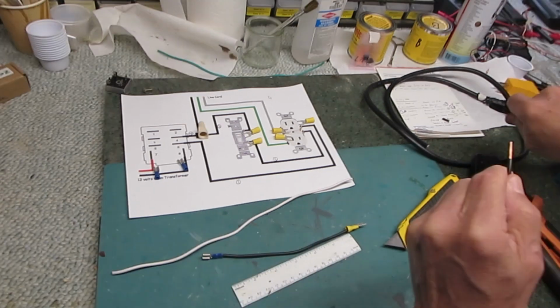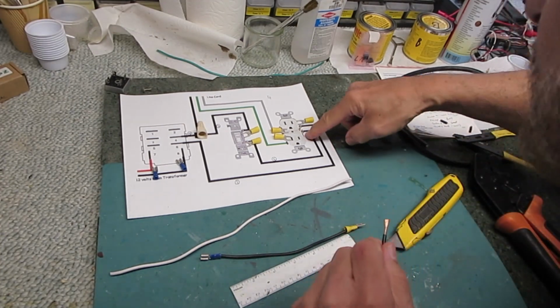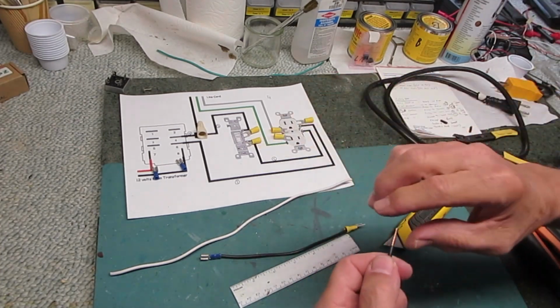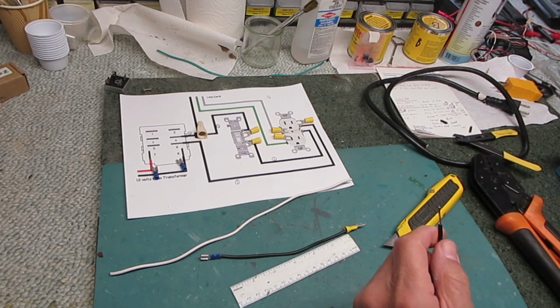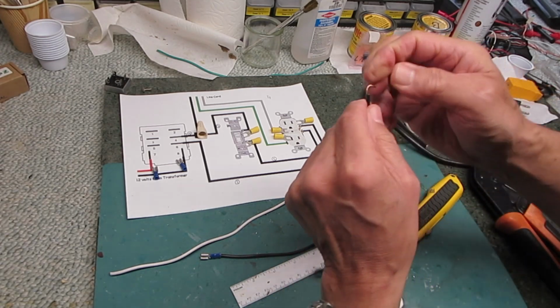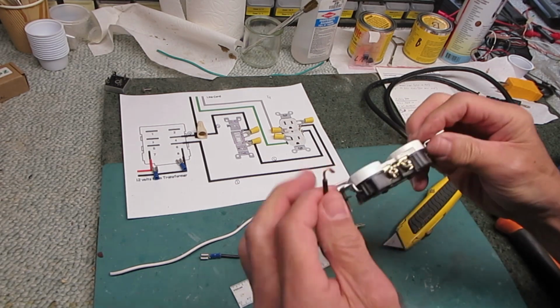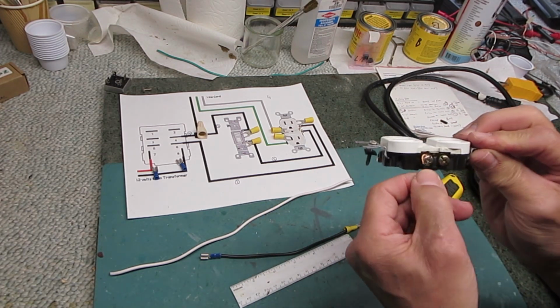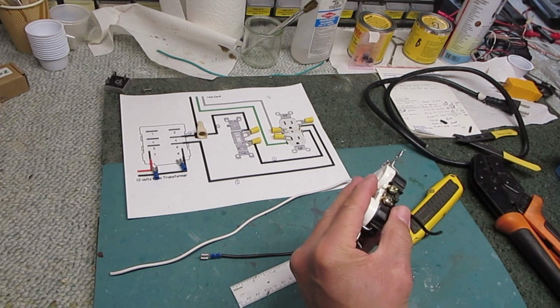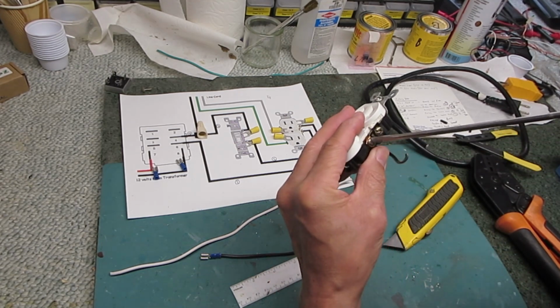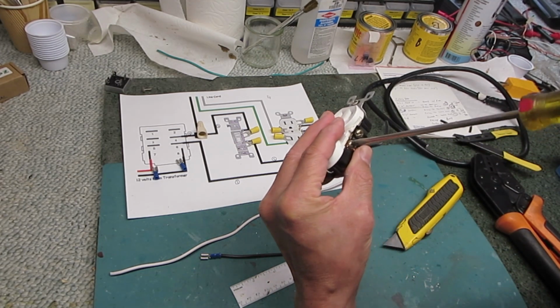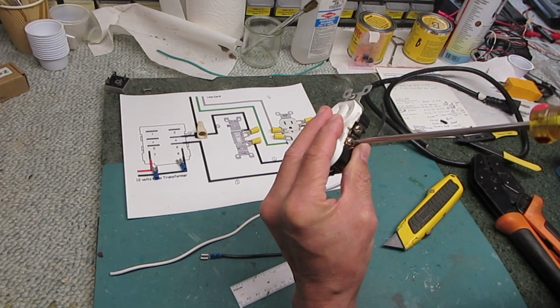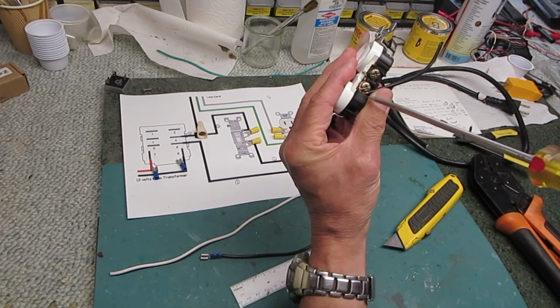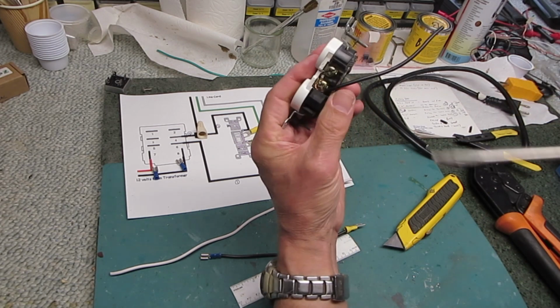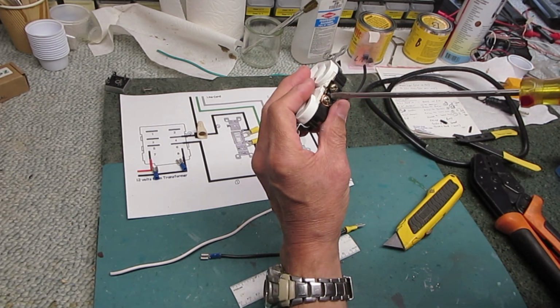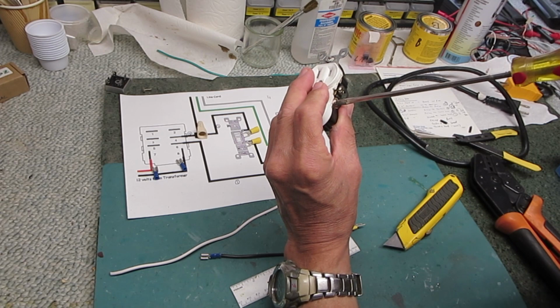This is going to be wire number 2, which is going to go from the receptacle to the switch. Now, if you just take this wire and make a hook in it and try to put it around the screw, it tends to spread the strands out and push it away from the screw. You can see it's coming out around there, and it's not really a good connection. You don't have all the copper under the screw. This is not a good way to do it.